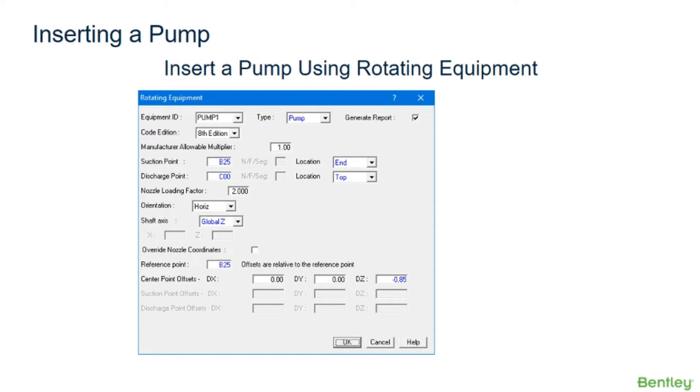To define rotating equipment in the model, you can select the Tools Rotating Equipment option. The Equipment command enables the user to define rotating equipment and to evaluate the forces at the nozzle and reference points using API 610, API 617, and NEMA standards.